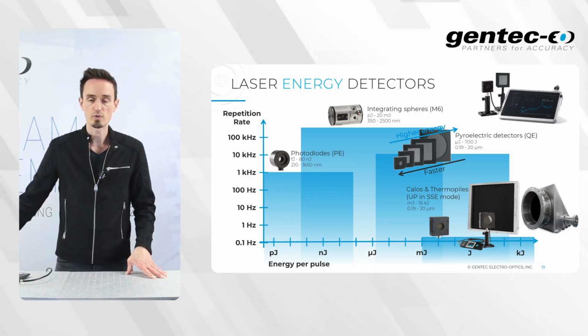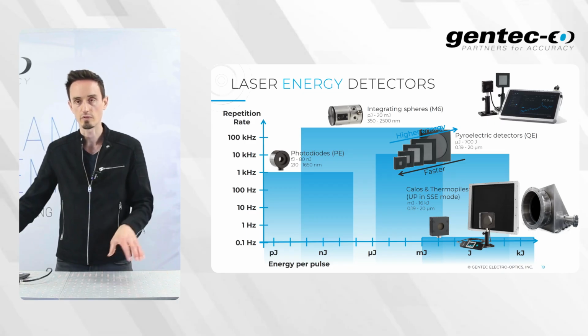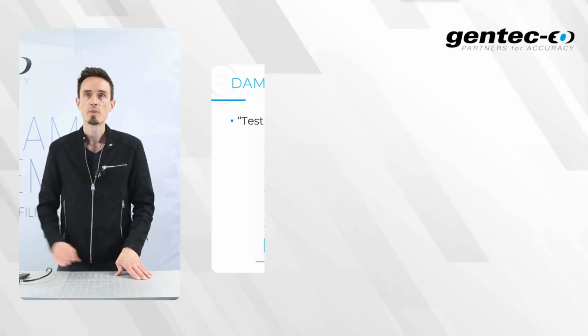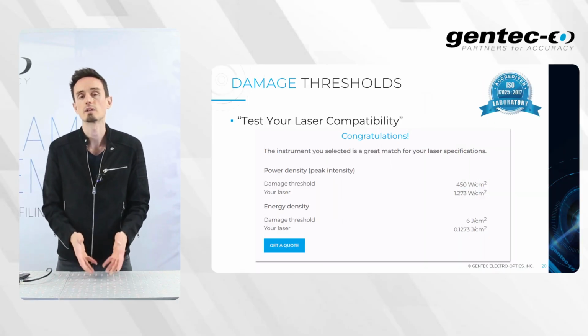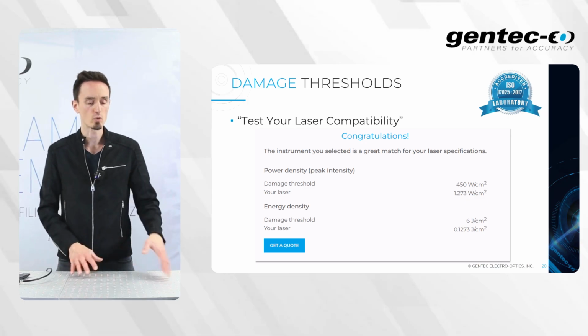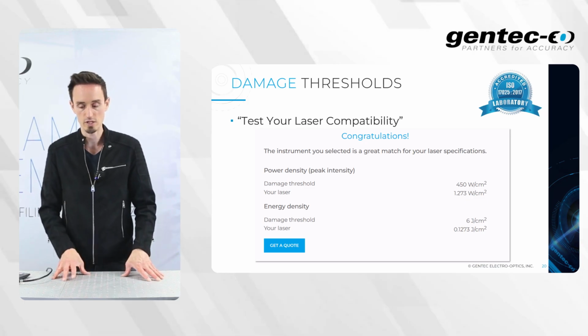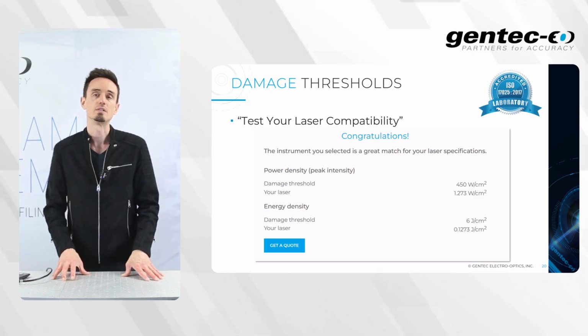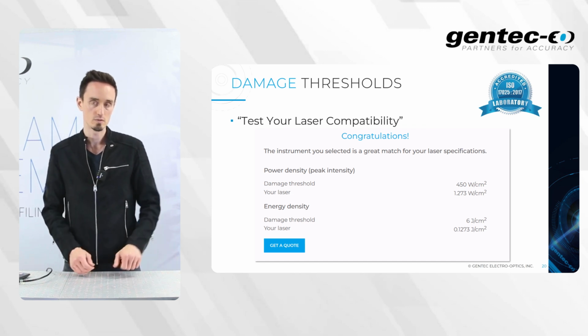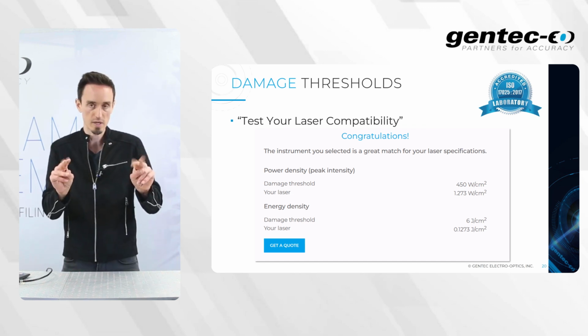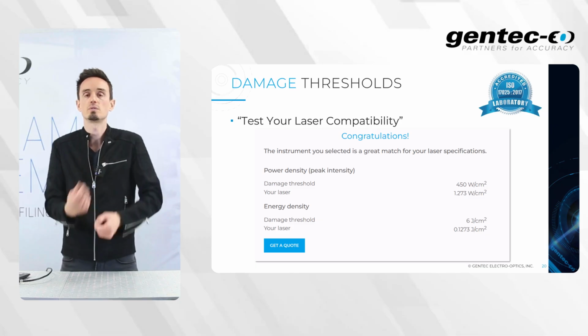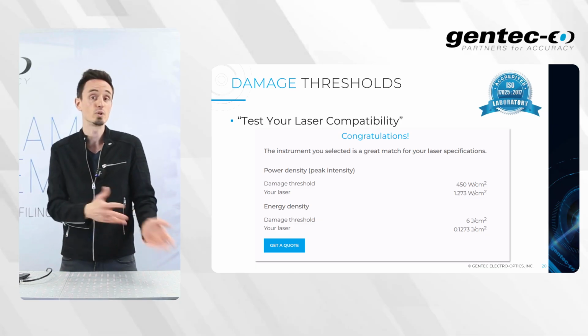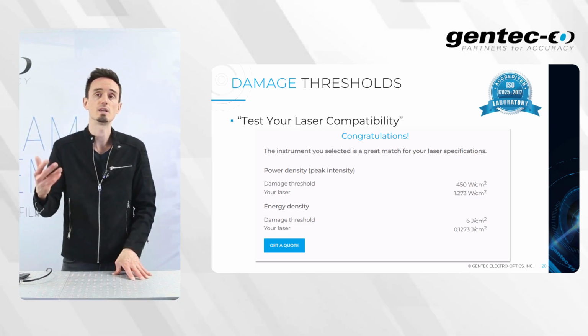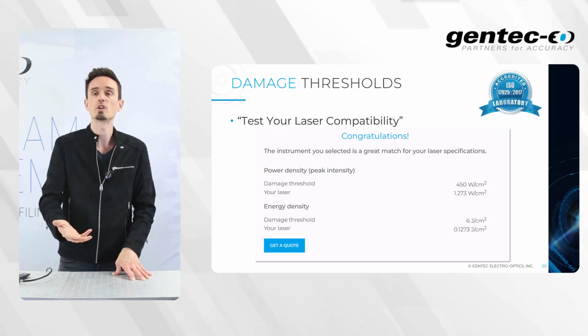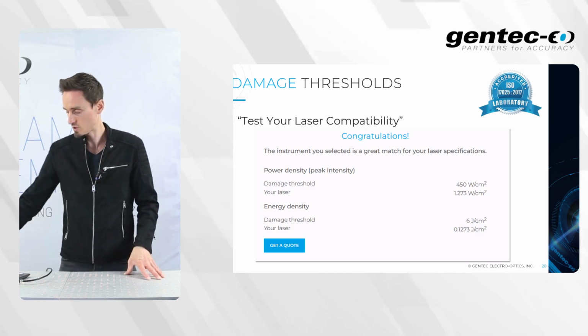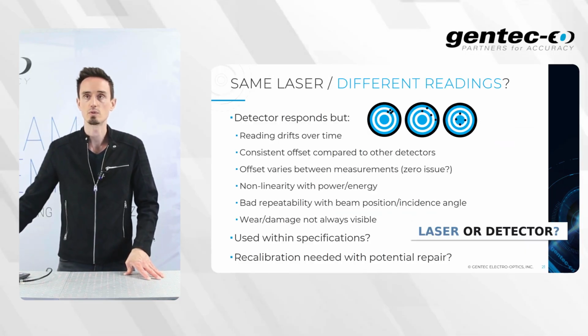The product finder is pretty efficient, finding the right spot, finding the right technology for those needs. And then, let's say you have a detector in your lab or in your facility that's been there for a while, calibrated or not, and you want to be sure it could be used for your laser line. There's a tool. You go to the product's webpage, you use this test your laser compatibility tool, enter your laser parameters, and you will get a go, no-go, and a calculation of the exact damage thresholds for those conditions. So, which could be very valuable to decide if you could use it or not.